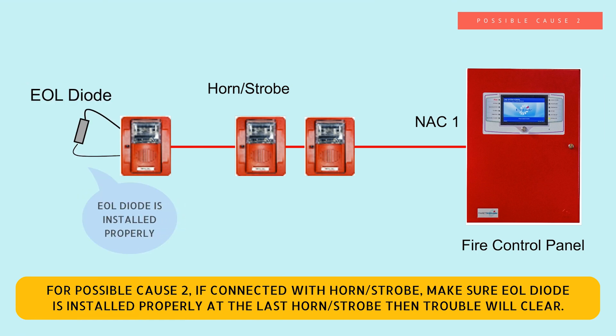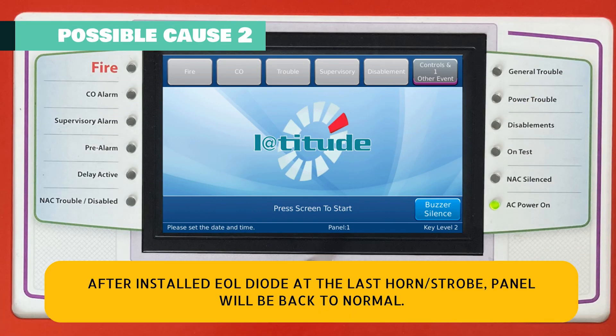For possible cause two: if connected with a horn strobe, make sure the EOL diode is installed properly at the last horn strobe. Then the trouble will clear and the panel will return to normal.